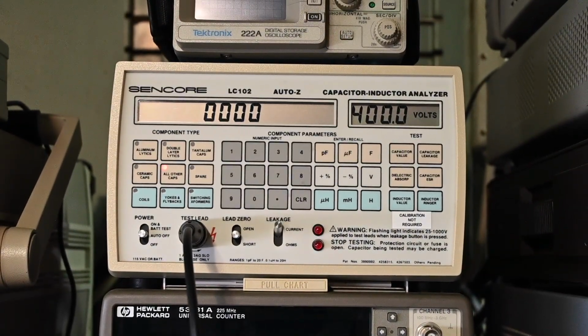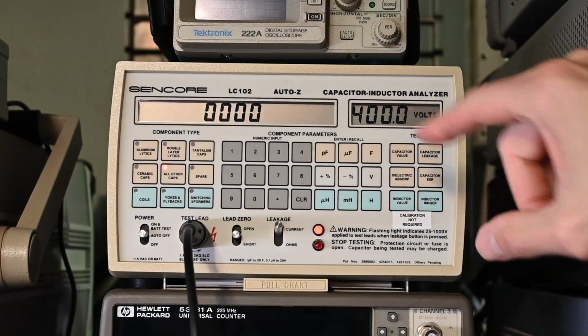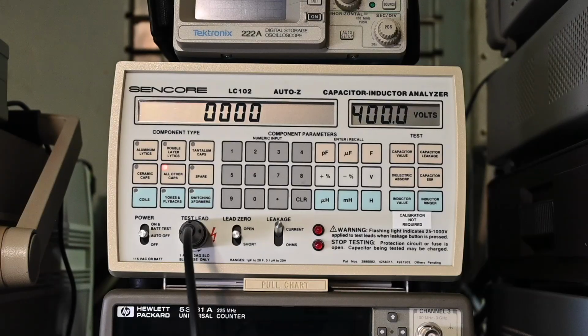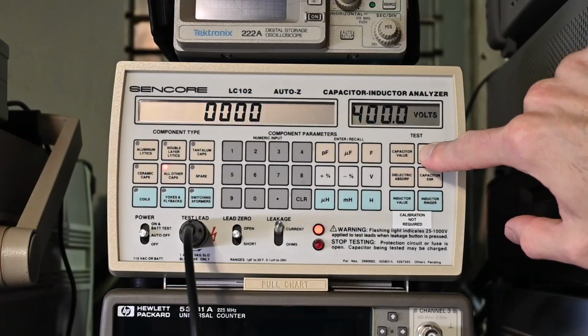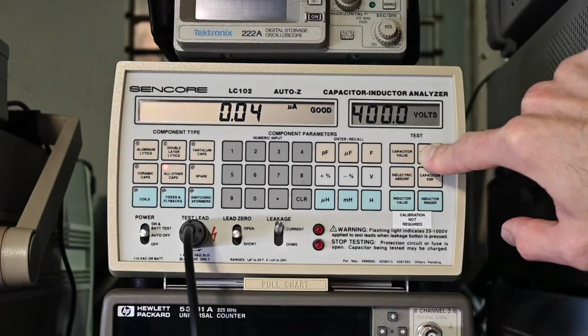So I've already set up the LC102 so that it knows what the expected capacitance value should be, and also the voltage, so 400 volts, that's the maximum rated voltage of that capacitor, and it'll apply 400 volts when I do the leakage test. So we'll start with that. So press this, and it will start to measure the current flow through the capacitor. So it starts at a higher value as the capacitor is charging, and it starts to fall, which is normal. So 0.15 microamps. It says 0.12 microamps is bad, but now it goes to good, so it may have been taking just a little longer to charge than it was expecting.